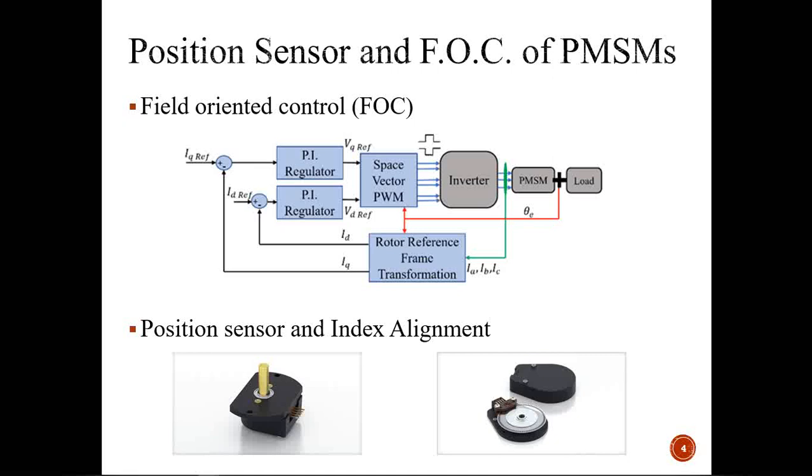In order to measure or identify this alignment, we use position sensors, and those position sensors have an index that will indicate your zero location. This position sensor is mechanically mounted, whether it's an encoder, resolver, or hall sensor. When mounting the sensor, you need to be very careful about this index alignment with the rotor zero.